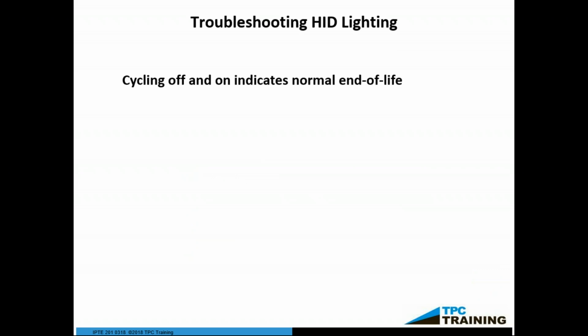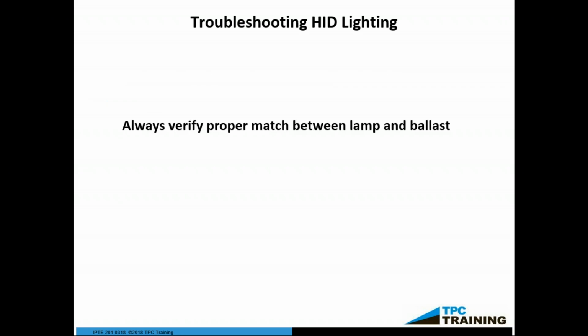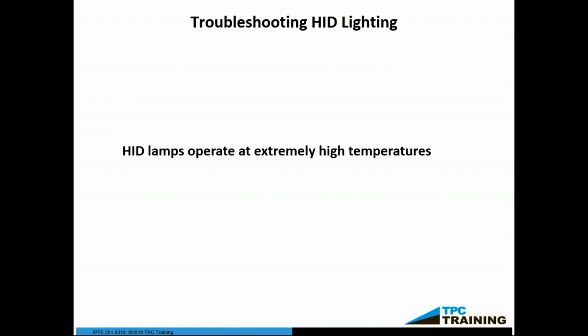Troubleshooting HID lighting. If the unit's cycling on and off, it normally signals the end of life, okay? But it can damage your ballast if the lamp is not replaced in a timely manner. You always verify a proper match between lamp and ballast. HID lamps operate at extremely high temperatures, and safety precautions are necessary. You cannot grab that, even with a glove, it's still going to be hot if it's on or cycling. Got to be careful you don't burn yourself. So you've got to look at safety.